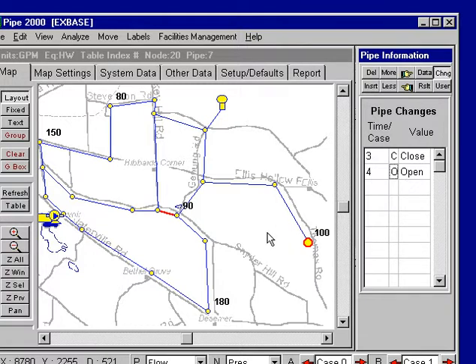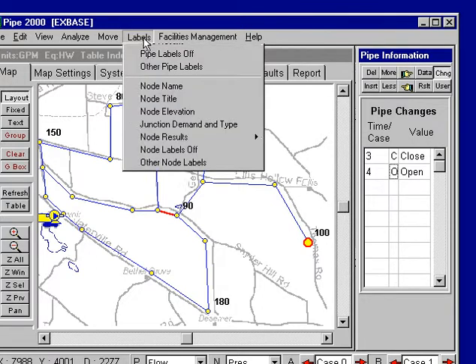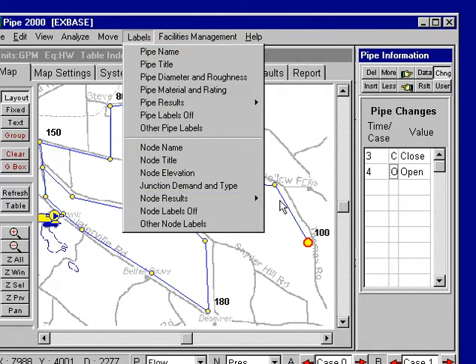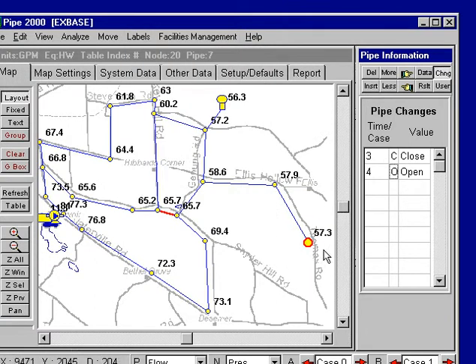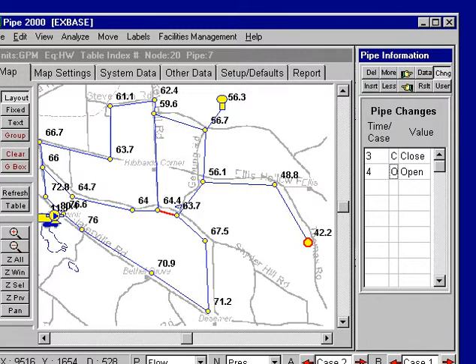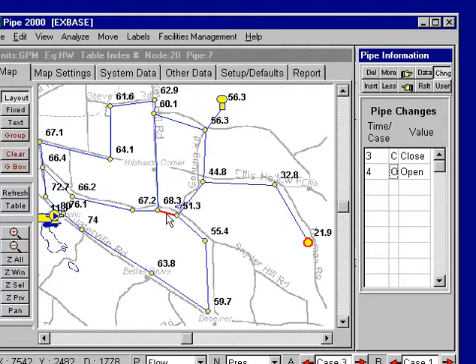This simulation has already been run for the first three cases, and we can look at the effects. I can turn on the pressures here. For the original data, they're 57. If I increase the demand, they're 50.7. Increase it a second time, it's down to 42 — that was at 200 gallons per minute. Increase it a third time, and it's down to 21, with this pipe closed, as we can see from the large pressure differential.